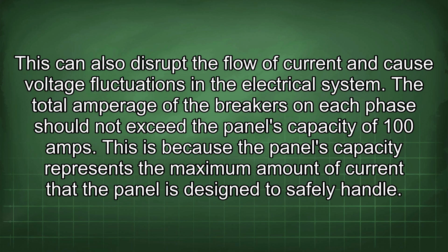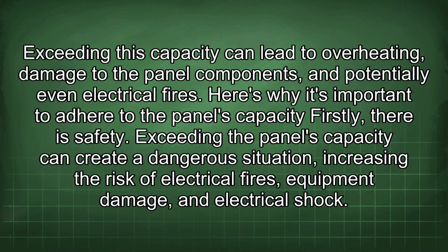The total amperage of the breakers on each phase should not exceed the panel's capacity of 100 amps. This is because the panel's capacity represents the maximum amount of current a panel is designed to safely handle. Exceeding this capacity can lead to overheating, damage to the panel components, and potentially even electrical fires. Here's why it's important to adhere to the panel's capacity.